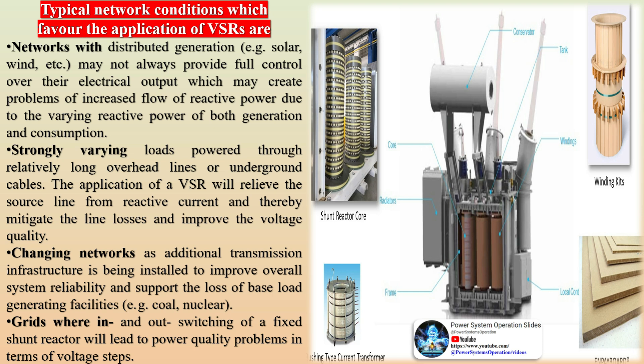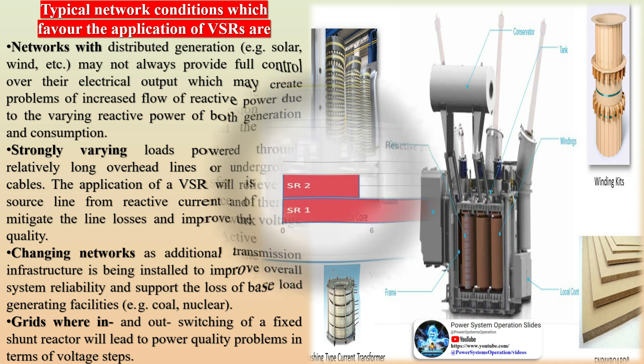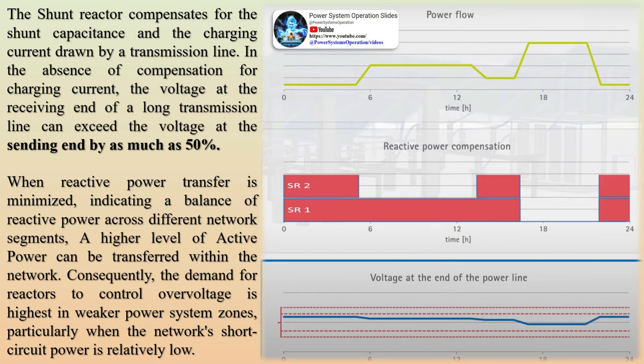Main technical benefits of VSRs compared to fixed reactors include the smoothing of voltage jumps, flexibility to the load, the ability to interact with SVCs, the possibility of relocation to another part of the grid, and the footprint reduction of a VSR replacing several fixed rating shunt reactors and circuit breakers.